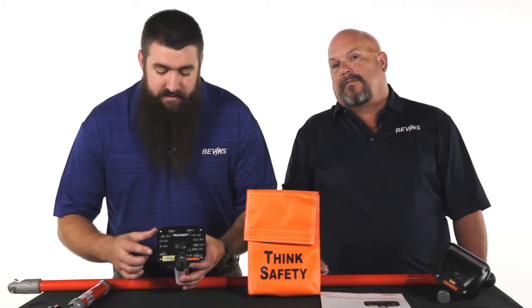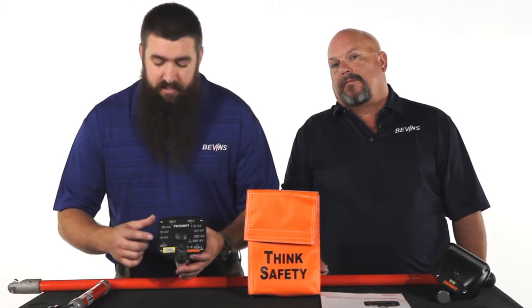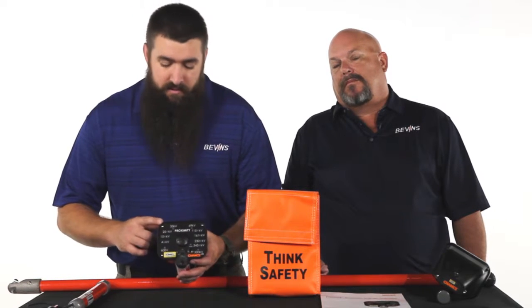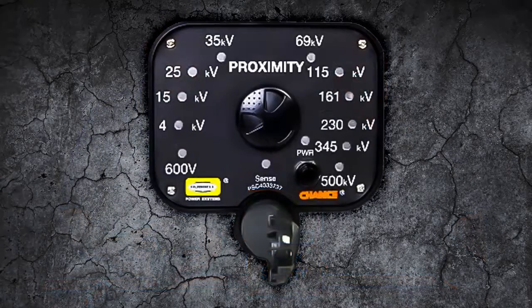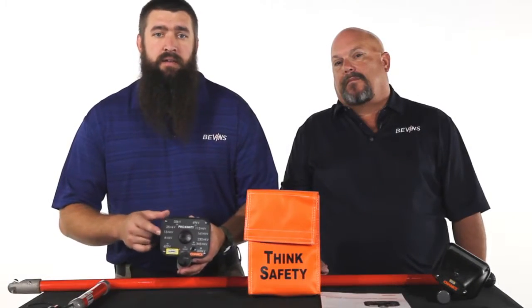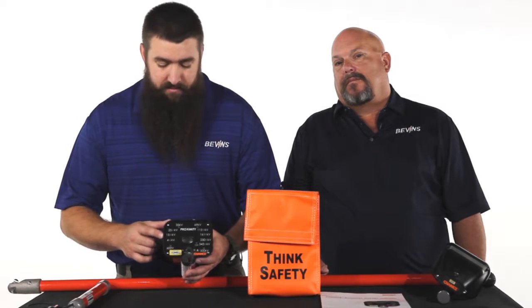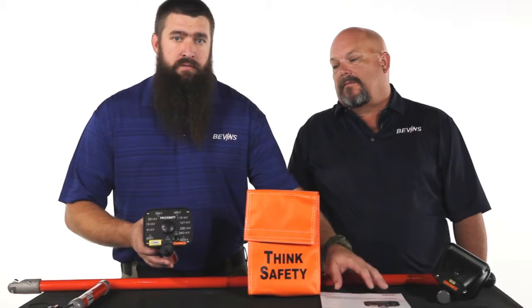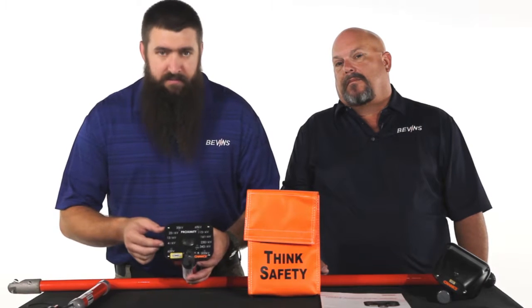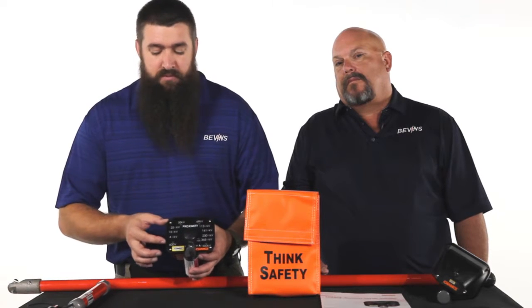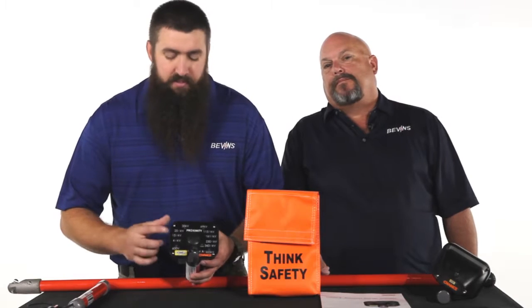So basically, we tried to select voltage ranges or voltage classes that are commonplace out in the world. For example, we have our 600 volt LED, 4 kV, 15, 25, 35, and so forth, all the way up to 500 kV. So if our 15 kV light is blinking at us and we're taking a voltage measurement, you can refer to the instruction manual supplied with each unit for a chart of that range broken down. So I happen to know that 15 kV is from 6.6 kV to 17 kV. So any voltage in between 6.6 and 17 will display the 15 kV light.